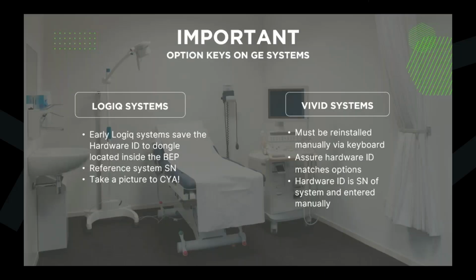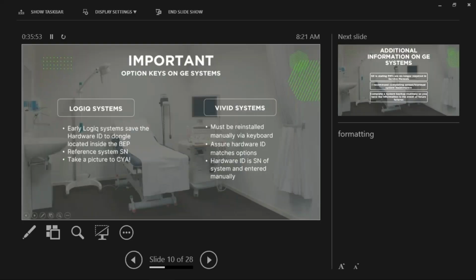Some important information to keep in mind when you're backing up older Logiq systems in particular. Early on, some of the computers had a little options dongle, or sorry, call it a hardware ID dongle inside the systems. So if you're replacing the computer or the BEP and you failed to move that USB dongle over that kept the hardware ID on it, if you had to recover the system, your license option string wouldn't work. So you want to make sure that the hardware ID matches.